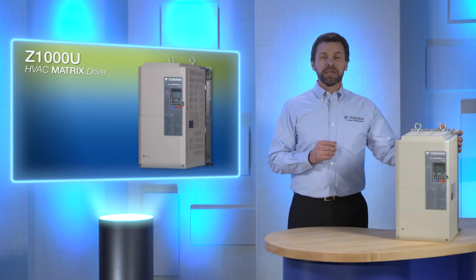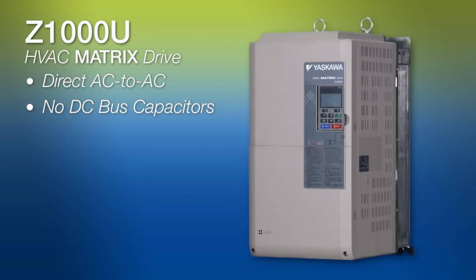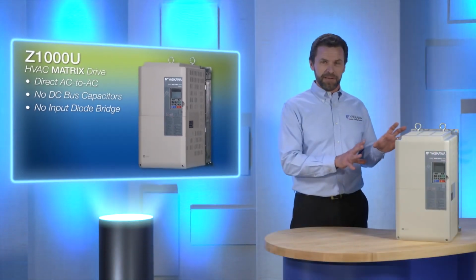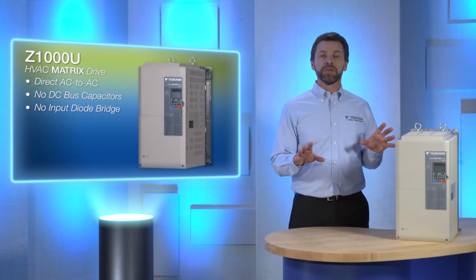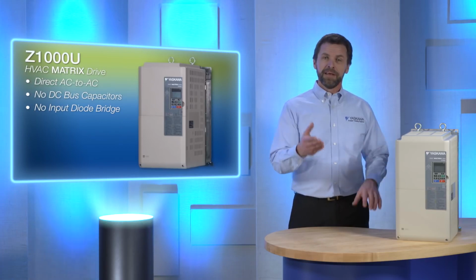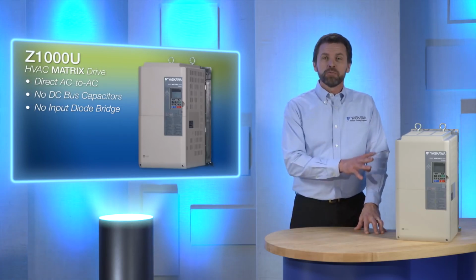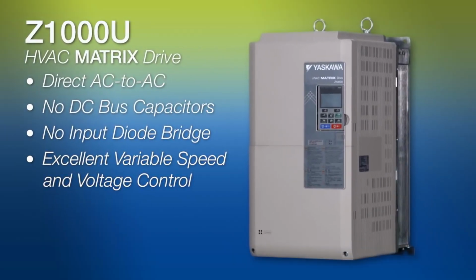Unlike typical harmonic mitigation techniques, the Yaskawa matrix drive is a direct AC to AC drive. Direct AC means there are no DC bus capacitors, which have a limited lifespan and may require maintenance. There is also no input diode bridge, which is a common cause of current harmonic distortion on the supply source. The matrix drive breaks free from some of the most fundamental components found in a traditional AC drive. Pushing expectations, the Z1000U provides excellent variable speed and voltage control for both induction and permanent magnet motors. The matrix drive achieves high efficiency through use of an innovative yet simple design.